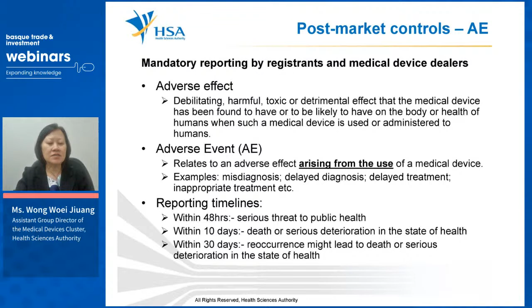The dealers also need to have compliance with advertisement control. They need to report adverse events and field safety corrective action. This is the definition of our adverse events and adverse effect, and we have specific reporting timelines for adverse event reporting to us, whether it's within 48 hours for a very serious threat to public health, within 10 days for death or serious deterioration in the state of health, and within 30 days where recurrence might lead to death or serious deterioration of health.